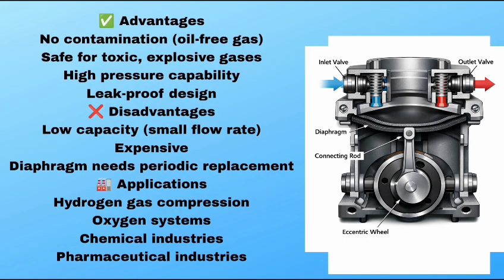Advantages of the diaphragm compressor: low contamination, oil-free gas, safe for toxic and explosive gases, high pressure capability, and leak-proof design. Disadvantages: low capacity, expensive, and the diaphragm needs periodic replacement. Applications: hydrogen gas compression, oxygen systems, and chemical industry.